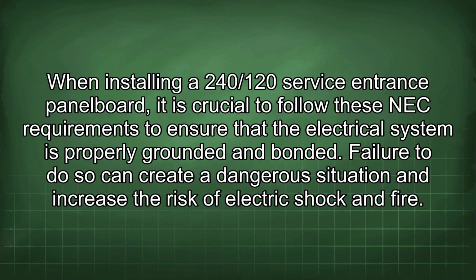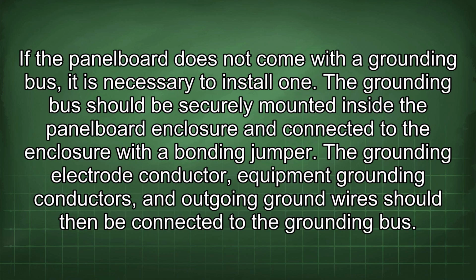When installing a 240/120 service entrance panel board, it is crucial to follow these NEC requirements to ensure that the electrical system is properly grounded and bonded. Failure to do so can create a dangerous situation and increase the risk of electric shock and fire. If the panel board does not come with a grounding bus, it is necessary to install one. The grounding bus should be securely mounted inside the panel board enclosure and connected to the enclosure with a bonding jumper. The grounding electrode conductor, equipment grounding conductors, and outgoing ground wires should then be connected to the grounding bus.